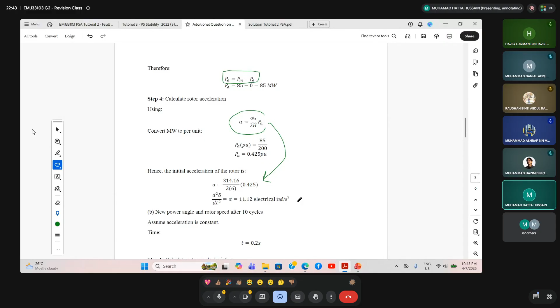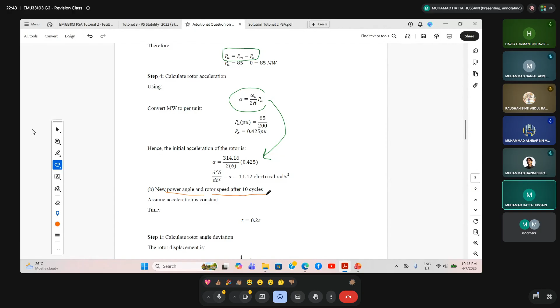So I have the initial acceleration of the rotor, d square delta over dt square, equal to alpha, equal to 11.12 electrical radian per second square. And then after I found the initial acceleration of the rotor, I need to find the new power angle and rotor speed after the 10 cycle. I assume the acceleration is constant and the time is equal to 0.2 second. So I need to calculate the rotor angle deviation. Okay, deviation means this one. This is actually the deviation.